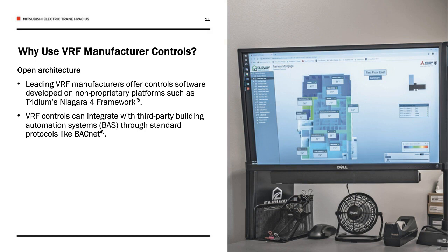So let's take a rooftop, for example, that has nothing to do with Mitsubishi Electric. Let's say it's a third-party rooftop that has a BACnet-enabled control board. That unit would probably have 30, 40, 50 points of information flowing through that BACnet interface, and we would be able to pick up, display and control the unit based on all 50 of those points. Now, not every manufacturer has an expansive list of control points, but most of them do.